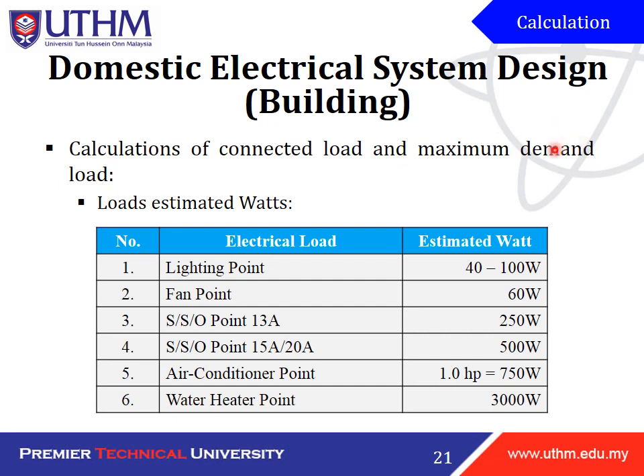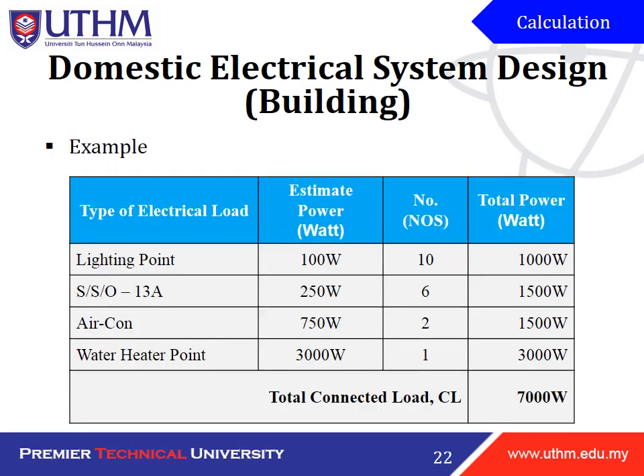Okay, this is the example of how to calculate the domestic electrical system design for a building. So calculation of connected load and maximum demand loads. So this is the estimated load in watts. We have lighting point, we have fan point, we have SSO point with 13 ampere, we have SSO point with 15 ampere, air conditioner point, and also water heater point, with the estimated watts listed here. So we have the lighting point with 100 watt with 10 nos. So to know the total power, we just multiply the number by the estimated power, and we have the value. Same goes for the SSO point, aircon and water heater point. So when we have the total power, we can calculate the total connected load.